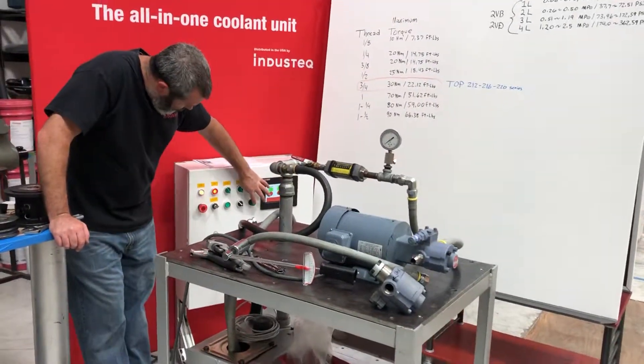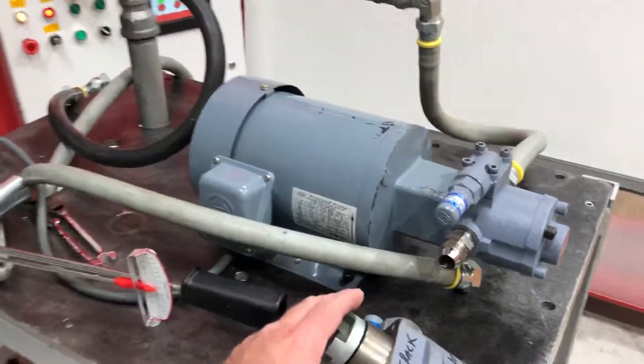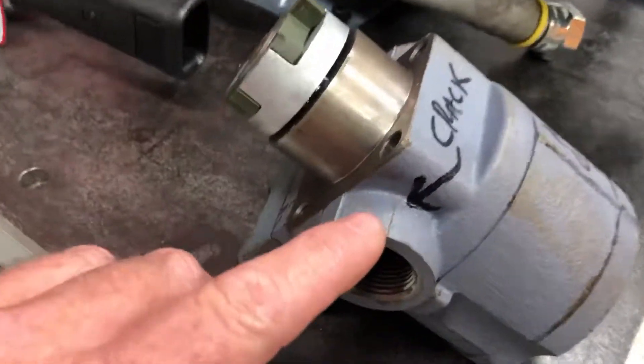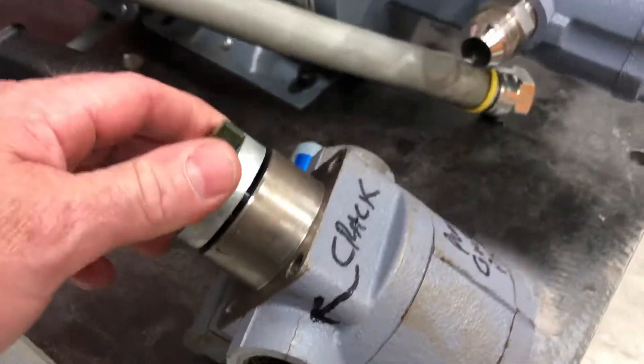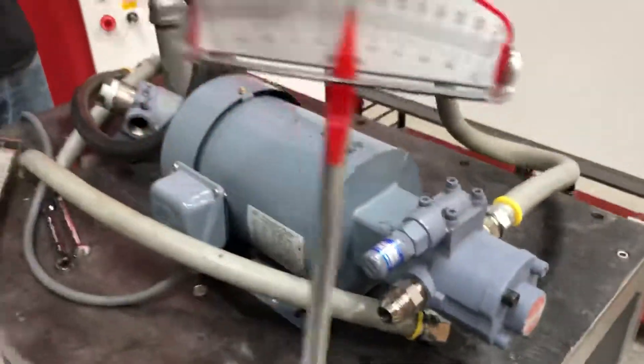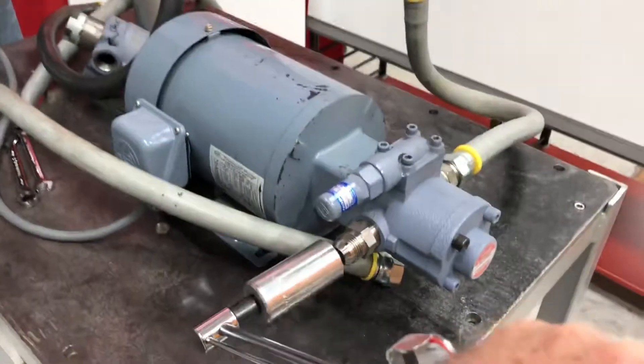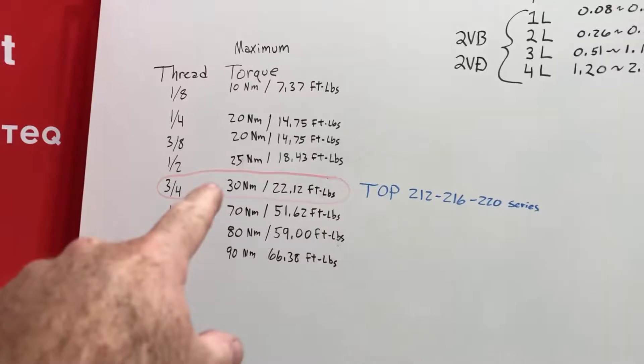This is Alan with Industeq representing Nippon oil pump. Too many times we see customers over-tighten the casting, so this is basically to show the maximum amount to tighten the fittings that go on here. Normally just a torque wrench is needed for this. I made a little chart up here — this is a three-quarter fitting.